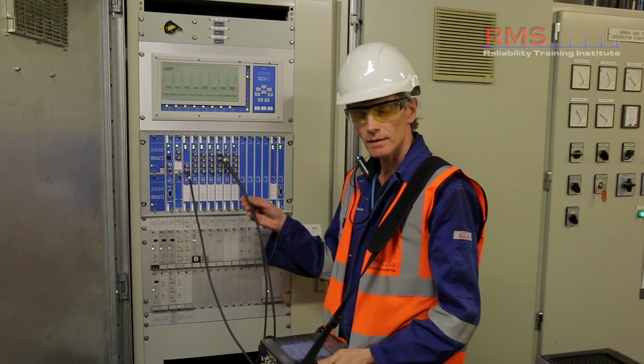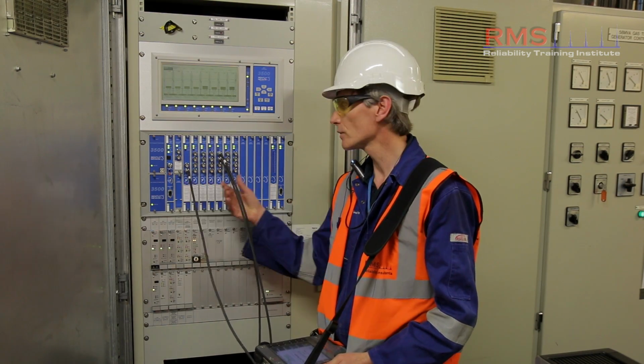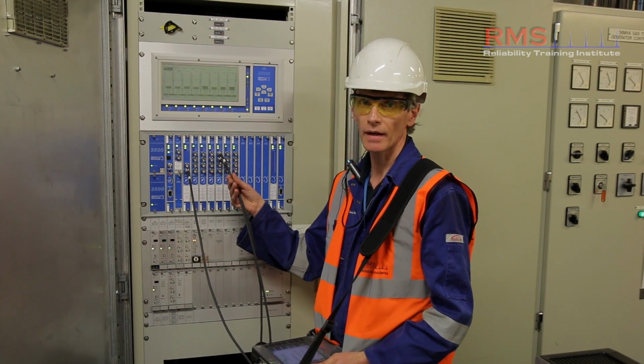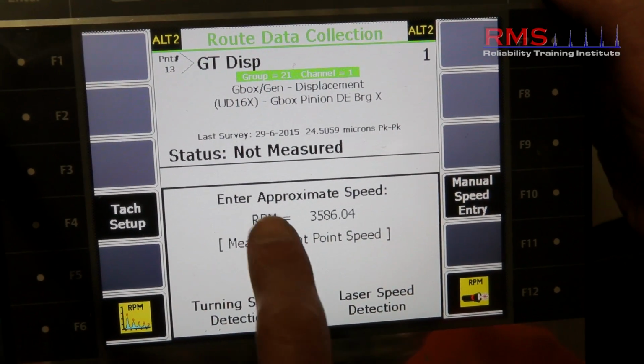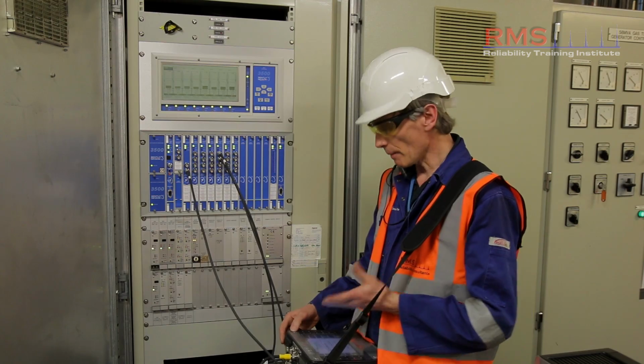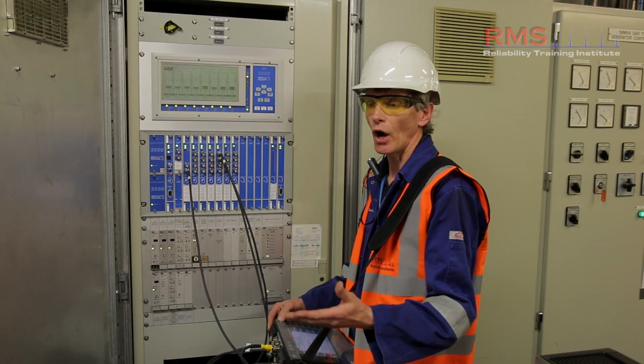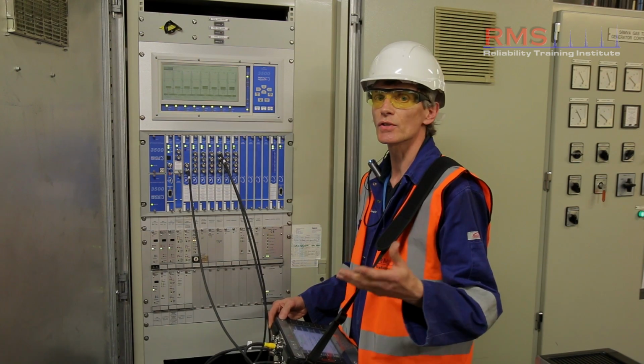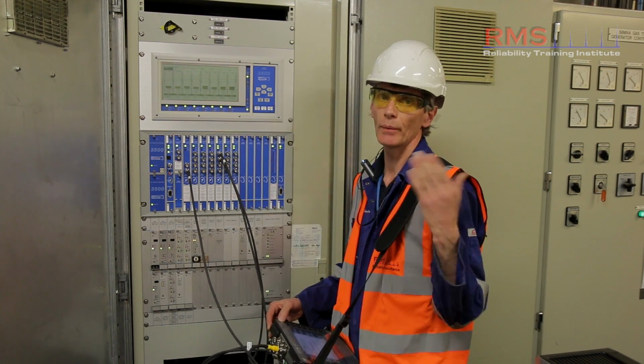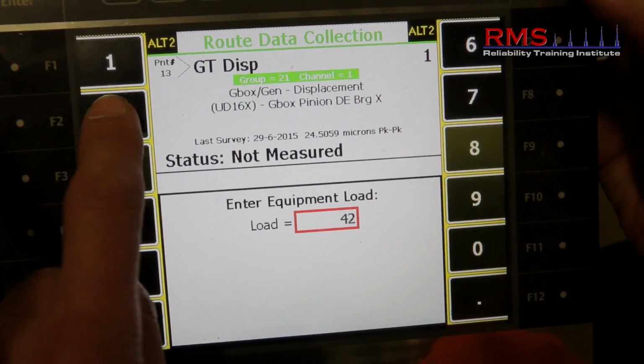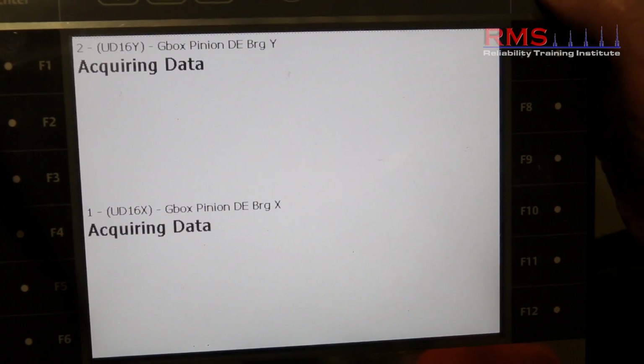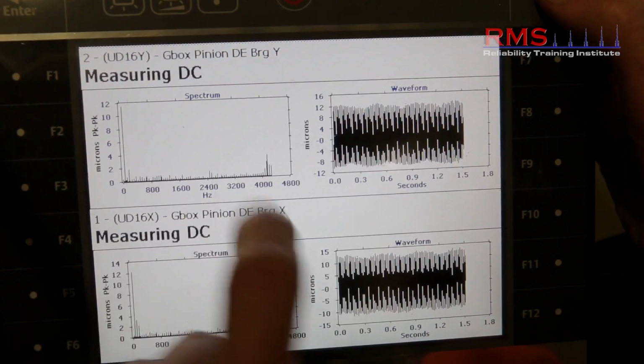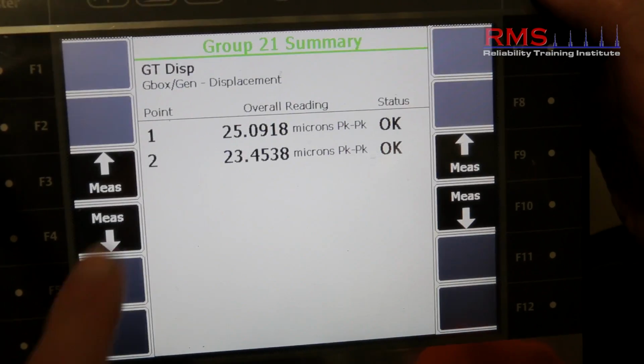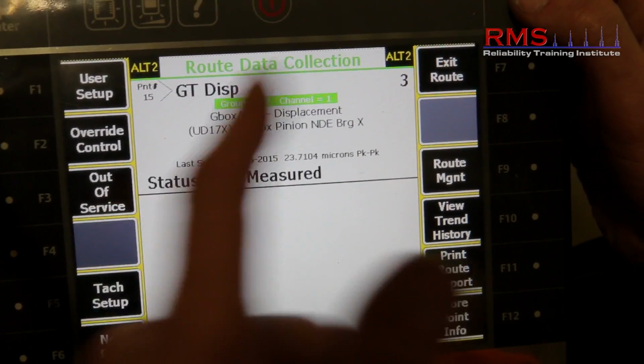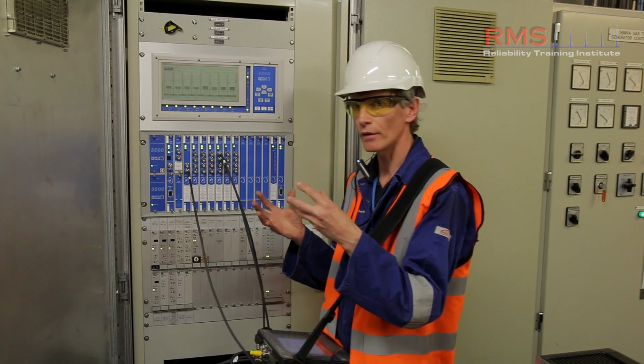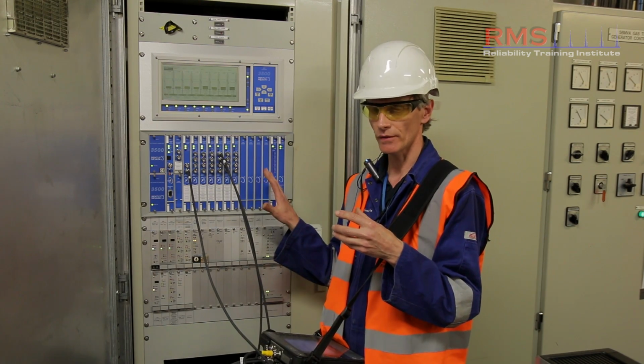A key point here is we're going to collect the data simultaneously. We've got a reference, a trigger to trigger our collection from, and indeed the timing of that collection as well. The speed is currently read out on the screen. I can clearly see the speed updating. And most importantly as well, we've got to think about process parameters. I would enter in flow rates, I would enter in temperatures and so forth, but equally before I start my vibration readings, I would record the load. So I'm just going to type in the load here, and then I'm going to collect the actual FFTs. I'm measuring the FFT raw dynamic signal coming out of those X and Y probes to look at the motion, to look at the heartbeat of the machine, providing more predictive information, more detailed, more finite changes that may be occurring. That's an important building block to add on to the protection that exists in the first place.